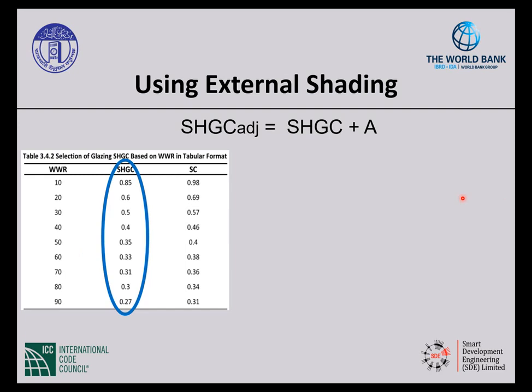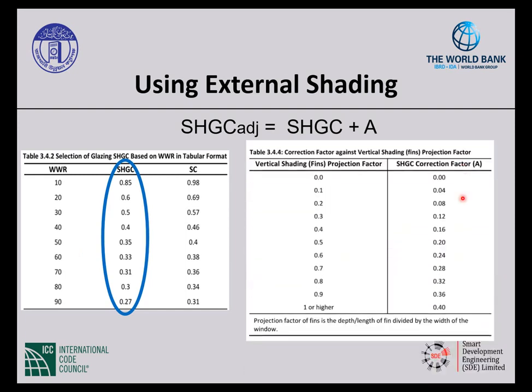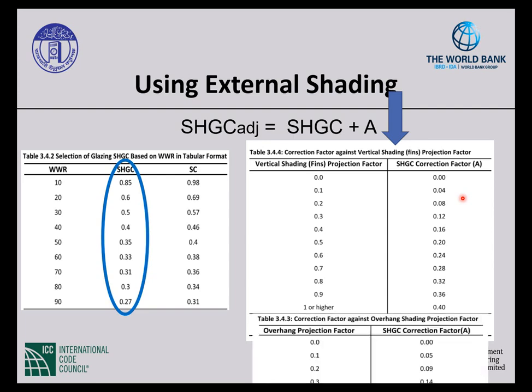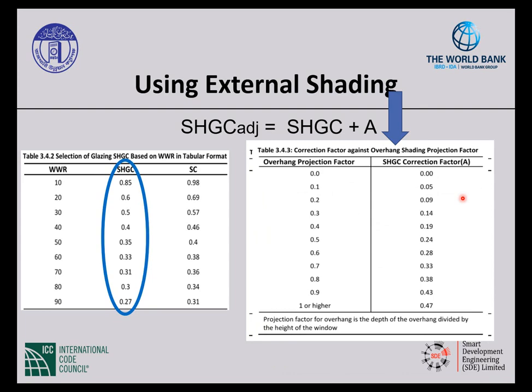So we find our solar heat gain coefficient. Then we go over here and determine what kind of shading we're putting on the window. Now it gives you credit for shading with fins, which is vertical next to a window, or it gives you credit for shading with an overhang, so horizontal over the top of the window. Which kind of shading? There's two different tables. And so then it asks you, all right, what's your projection factor? How big is that projection? So that we can determine how much you're really protecting the window, so that we can give you your projection factor or your solar heat gain factor. So let's look at how this works.